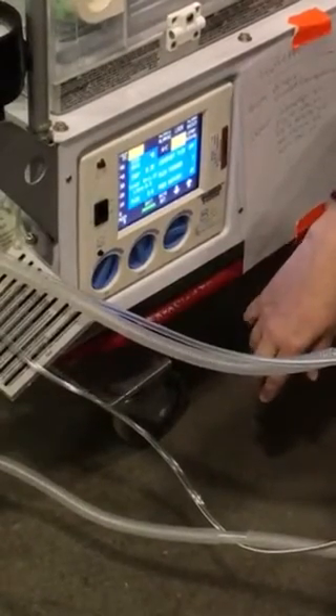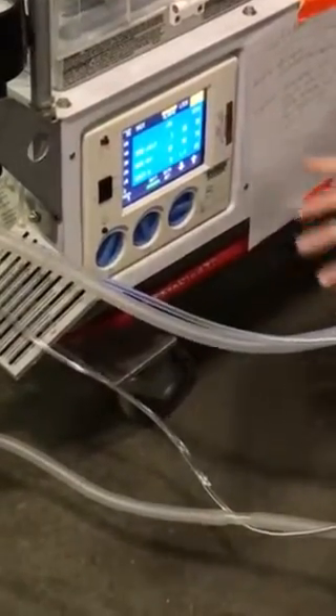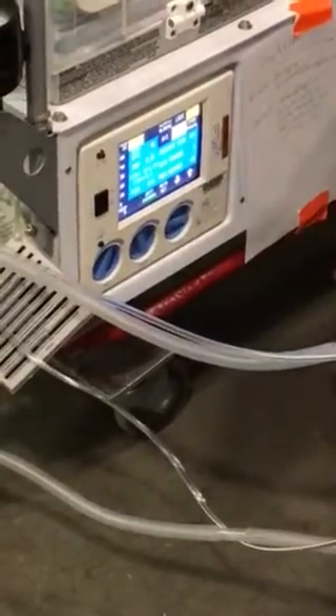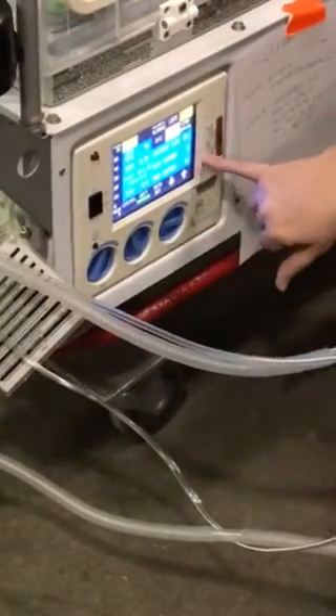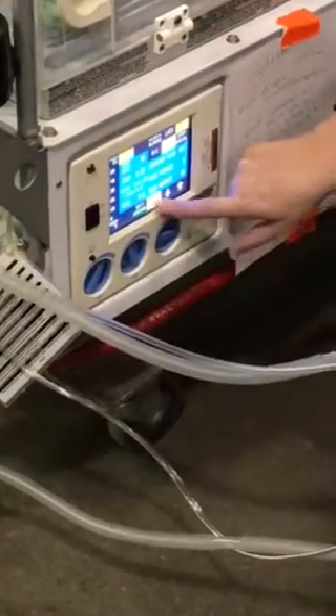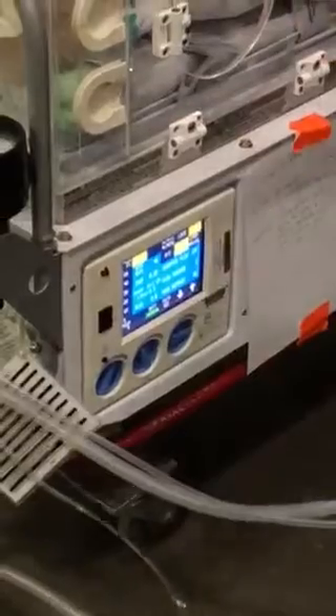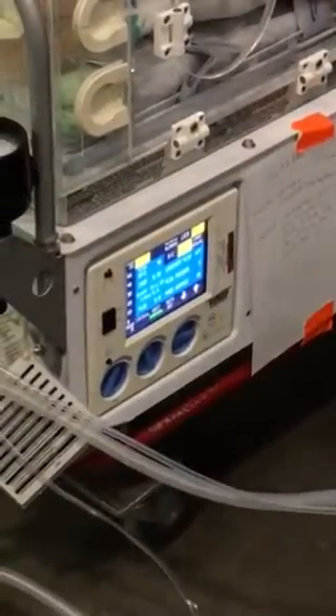So one of the things I like about this ventilator is, once you get all your settings the way you like them, so we have a rate of 49, time of 0.35, our flow is at 8, pressure support of 10, flow trigger of 5, and we're in SIMV and reading about 20 over 5. Once I have all those the way I want them, if I hit auto set twice, now it's going to set my alarms based on my settings. So that's a nice thing. Based on the settings we chose, it'll just default the alarms.